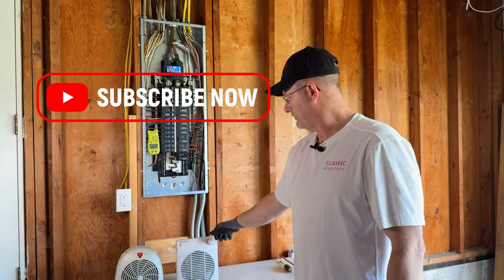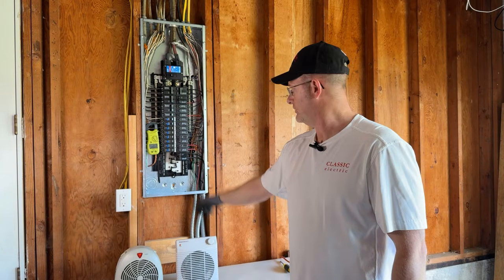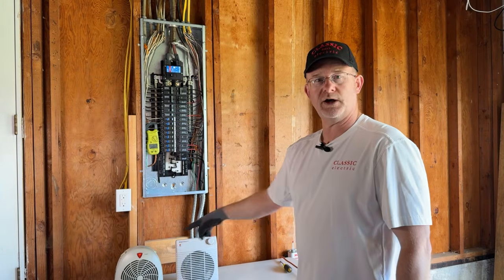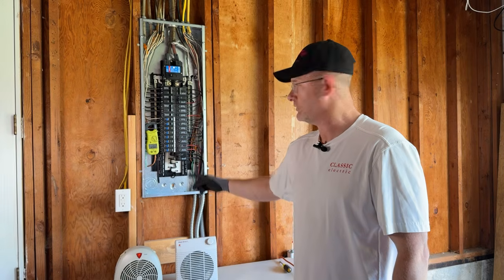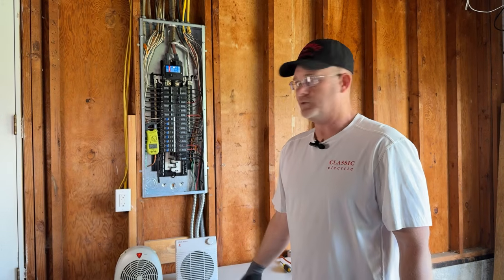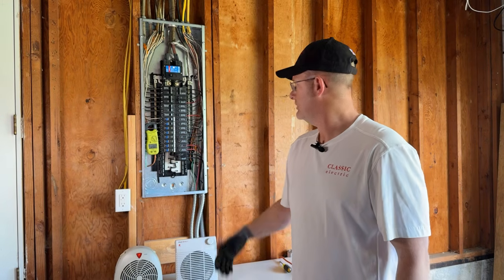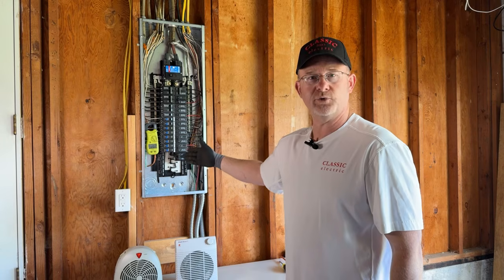Well, what do you think is going to happen if I go over to this one, I turn it on to high? Well, this one on high is 12. It's the same wattage as this one here. I turn this one up, we're going to go right to 25. Well, geez, you're 10 over on a 15. You're going to be 5 over on a 20.